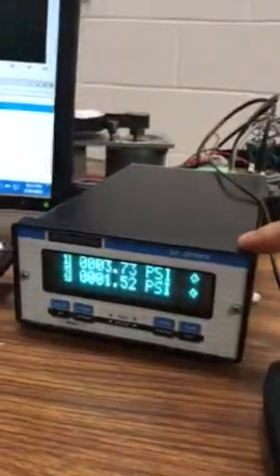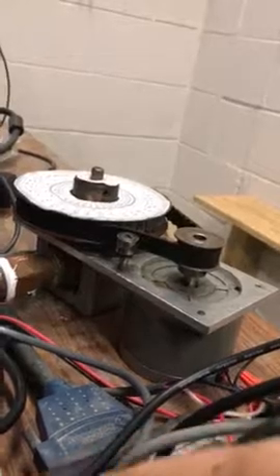I have the BNC 2110, and you can see here is the setting. It's an FS setting, floating signal. First of all, as you can see, the signal comes from the transducers and goes in as an input to the SC Sensotech, and you can see the pressure now is increasing. Channel 1 is this one, close to the valve here, as I show it to you. Channel 2 here is the upstream one, close to the tank. So this is the Sensotech I am using, and as you can see, there are signals coming here. I think the 6 pins here are 4 in, and 2 of them go to the BNC here.